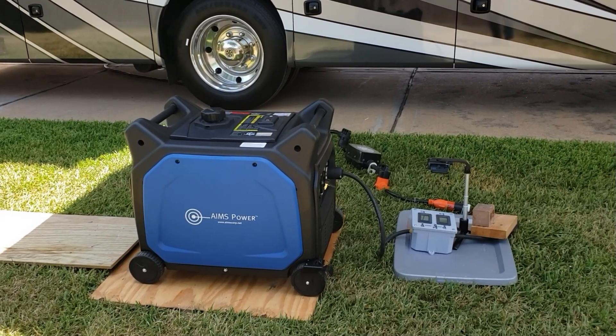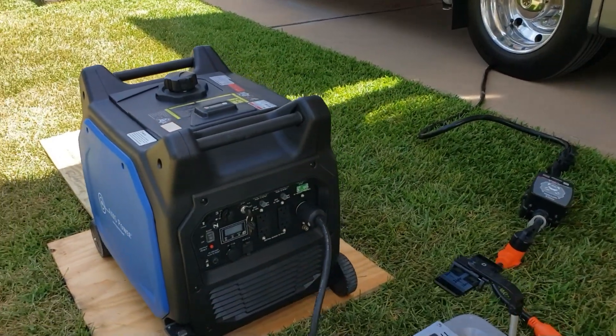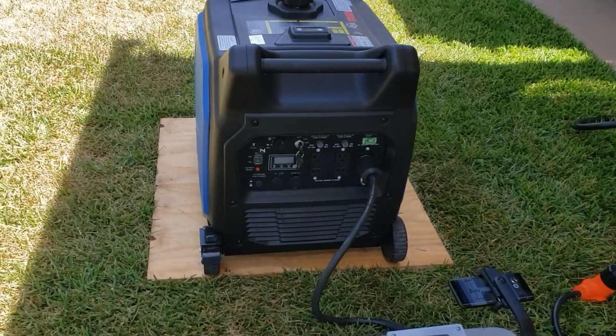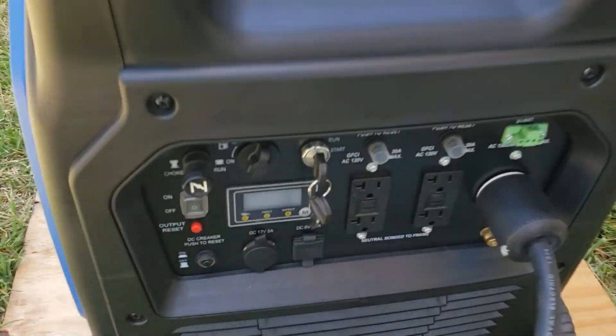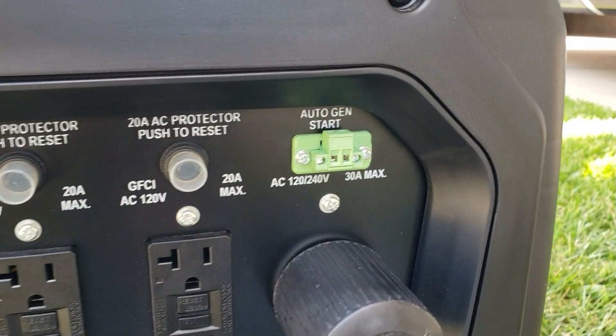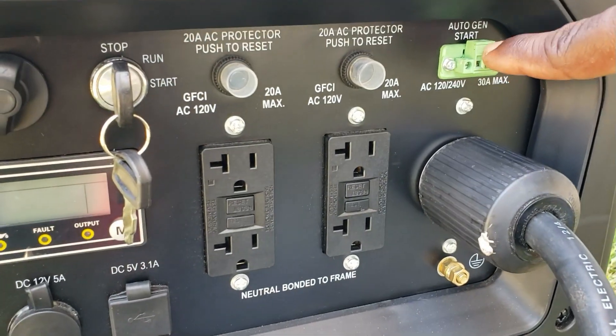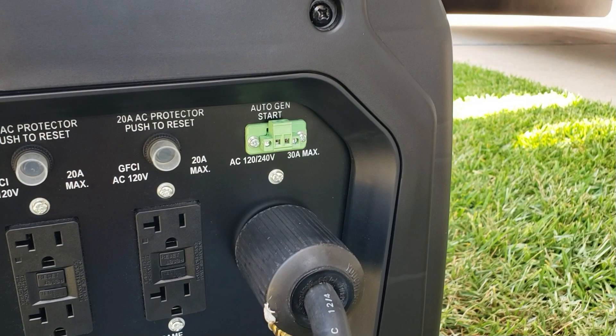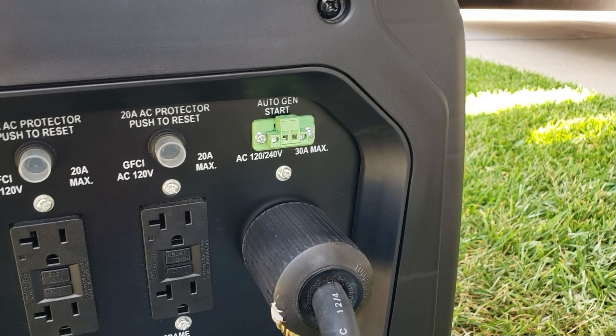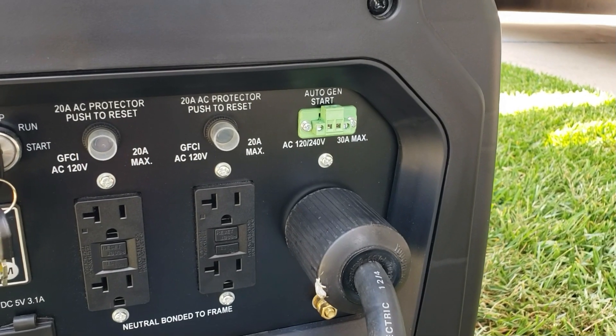Welcome back to the channel. Today we have the AIMS Power 6600 — a 120 volt 240 volt ultra quiet inverter generator. Most of you are really going to like this because it not only has a nice display up front, it also has an automatic gen start. It's just two wires — you install a switch, it's an open/closed loop. Turn it on and the generator starts; turn it off and it stops. No power required.